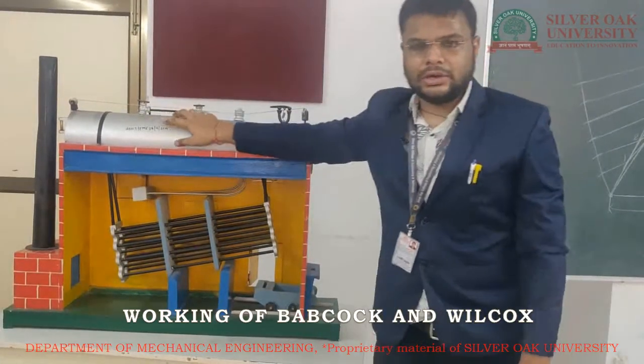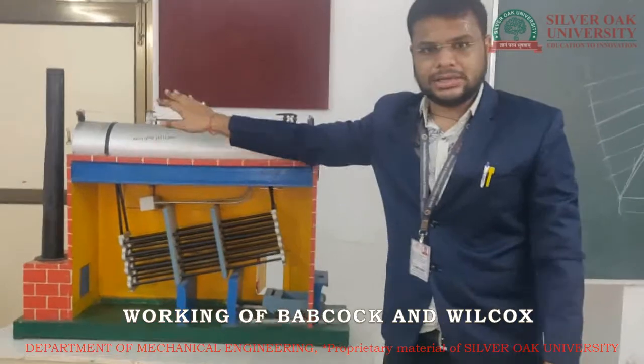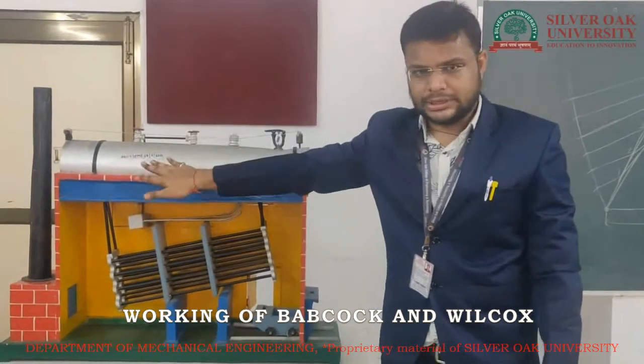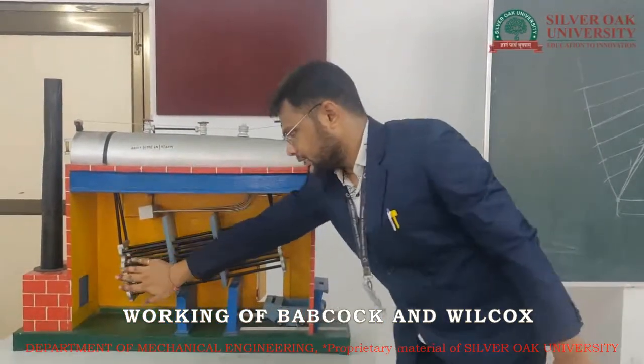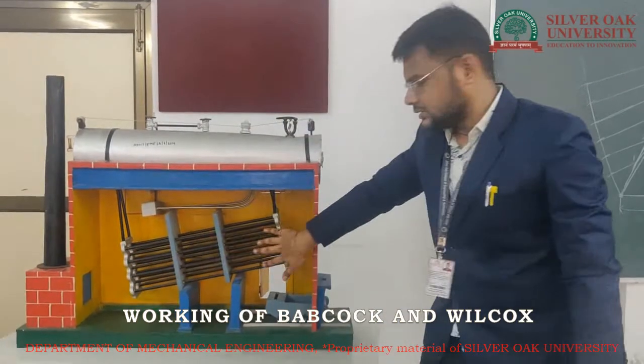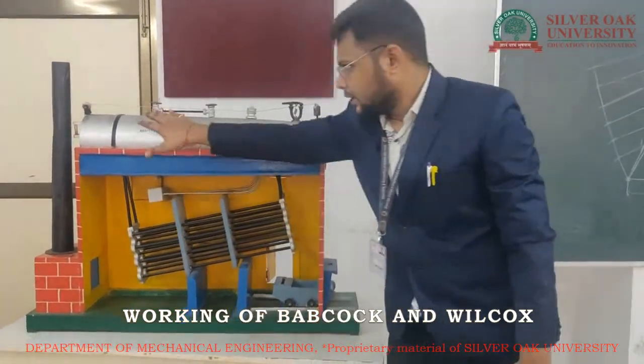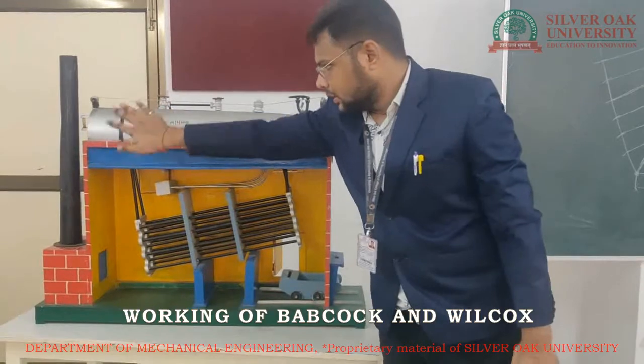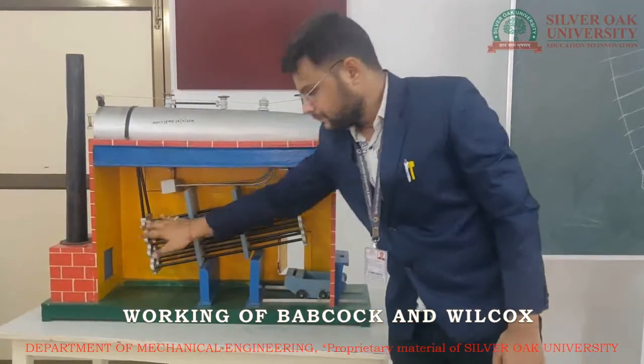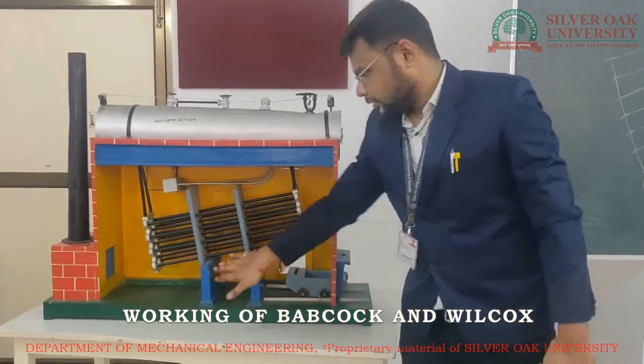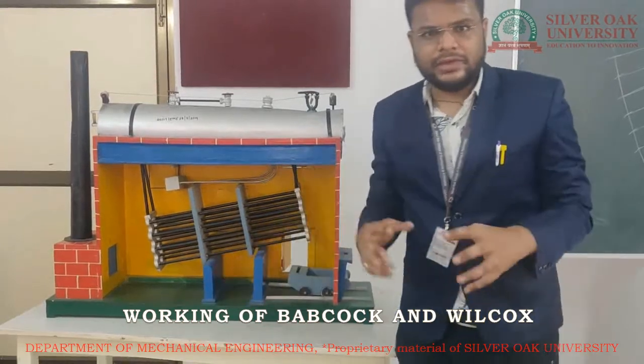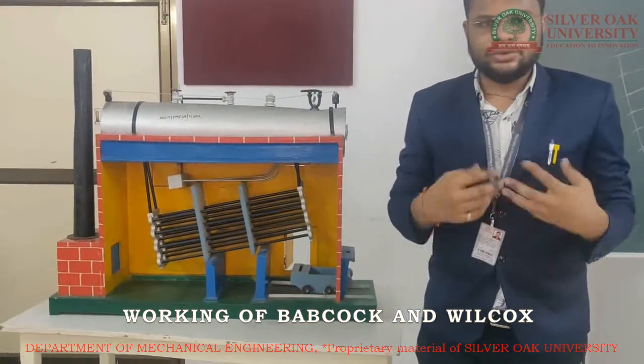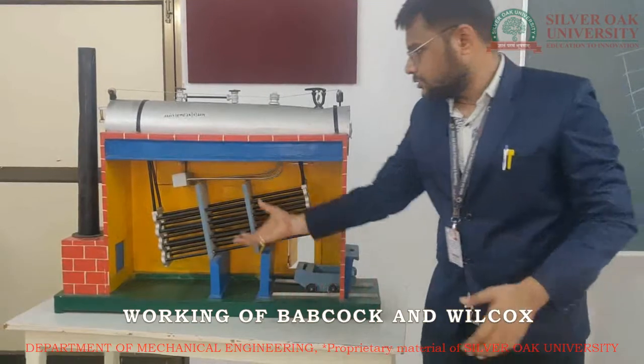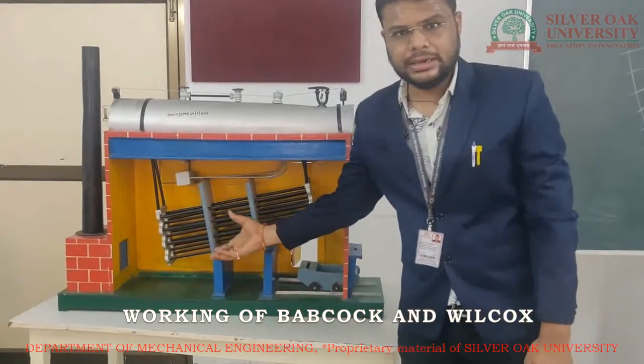Now after filling the water inside the boiler, the water comes from the water drum to the down take header. Now this is the down take header and this is the up take header. After the water comes to the down take header, on the damper or in the grate area we introduce the coal. And due to the combustion of the fuel, it produces the hot flue gases over here.